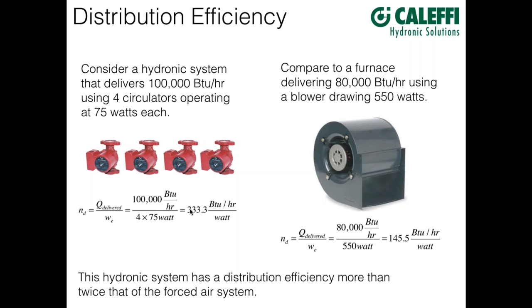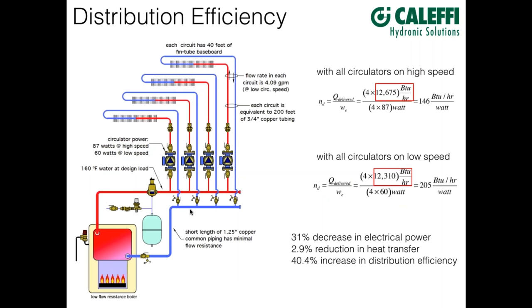Some slides started comparing multiple circulator systems and zone valve systems. A quick comparison: running four circulators on high speed at 87 watts each, where each zone delivers 12,675 BTUs per hour, gives a distribution efficiency of 146 BTUs per hour per watt. If we switch those circulators down to low speed at 60 watts each, notice that our heat transfer goes down a little bit — and that's a key consideration.